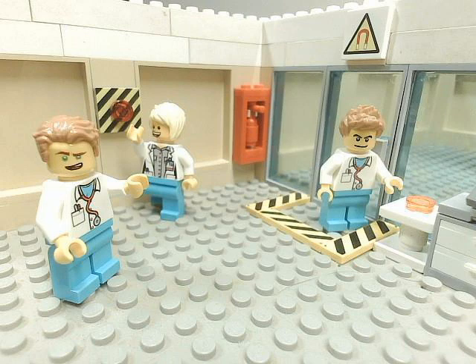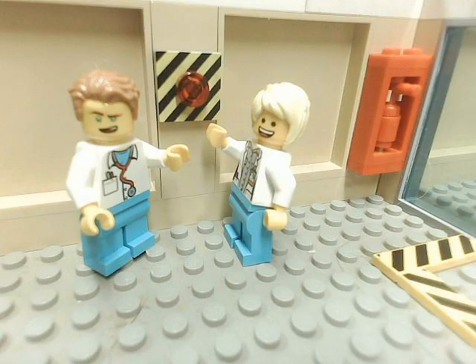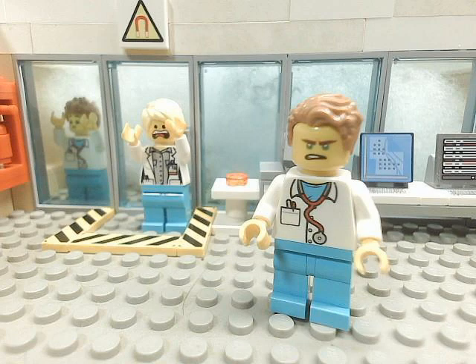There are always two emergency buttons at an MRI. One button turns off all electrical equipment and should be pushed if there is a fire — this button leaves the magnet on. A second button turns off the magnet. This button should only be used if a life is in danger, as it can cause dangerous situations including displacement of oxygen in the room or an explosion.